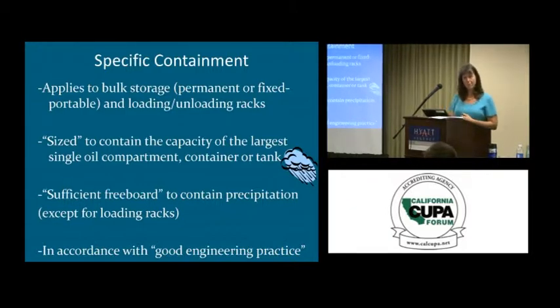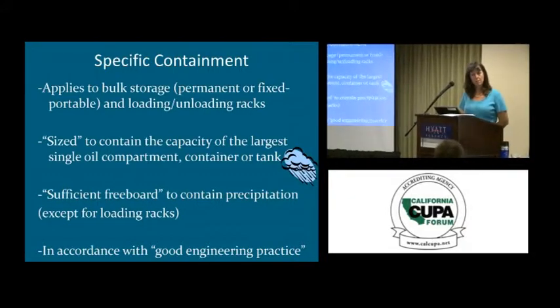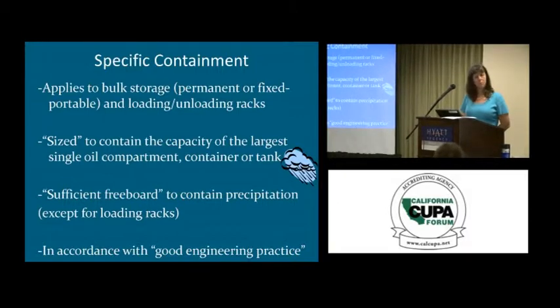Yes. Along that point, they took out the language that said to be impervious to oil for 72 hours. That was also in that guidance document at one point. And then you also have to, the PE is liable, and the inspector from the third party, either API or Steel Tank Institute, is also supposed to be looking at that. And that, to me, is why we really should have monolithic core, in my opinion, to prevent any sort of leakage because of that rule.